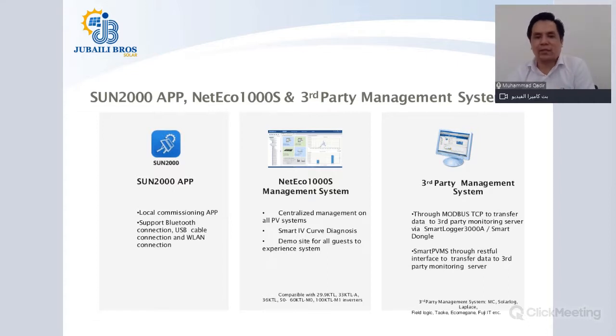Alternatively, you can also monitor the Huawei inverters' data on a third-party management system, such as Meteo Control, Solar-Log, and so on. You can do the communication through Modbus TCP to transfer the data to the third-party monitoring server via Smart Logger 3000A or Smart Dongle. Alternatively, there is an additional feature inside the Smart Logger, the FTP push function, through which you can directly send data to the third party's server.